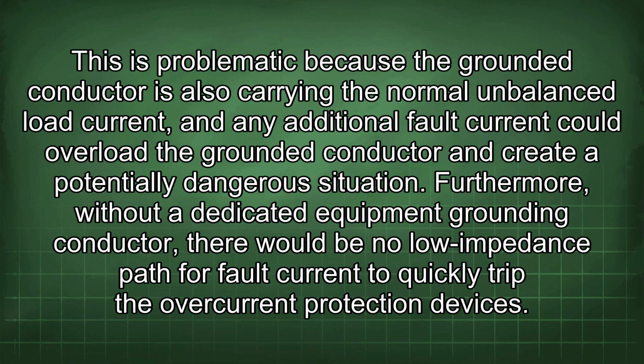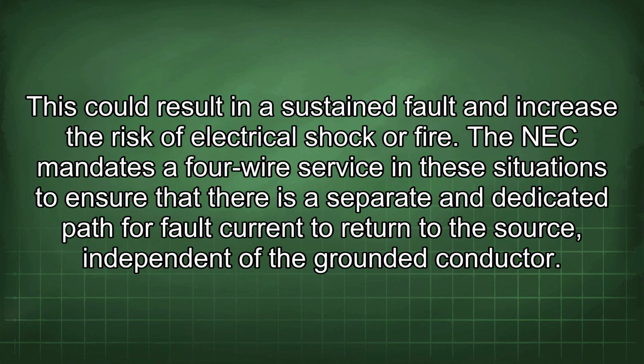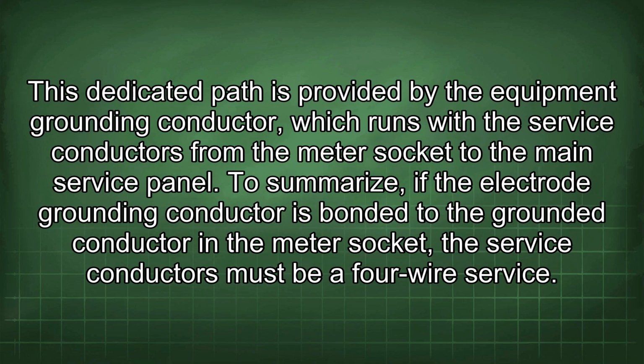Furthermore, without a dedicated equipment grounding conductor, there would be no low impedance path for fault current to quickly trip the overcurrent protection devices. This could result in a sustained fault and increase the risk of electrical shock or fire. The NEC mandates a 4-wire service in these situations to ensure that there is a separate and dedicated path for fault current to return to the source, independent of the grounded conductor. This dedicated path is provided by the equipment grounding conductor, which runs with the service conductors from the meter socket to the main service panel.